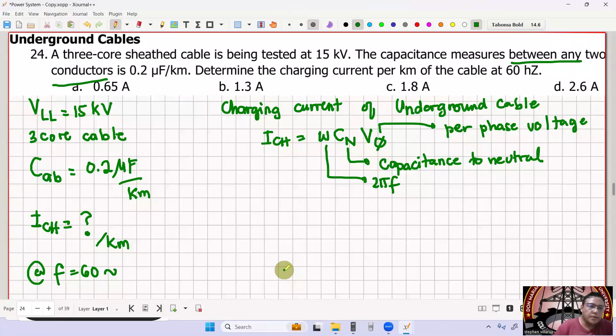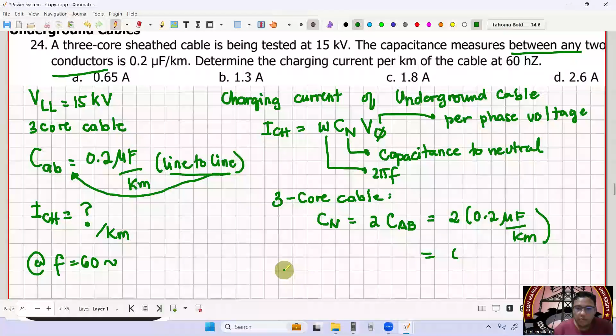Hindi siya line-to-neutral or capacitance to neutral, so paano natin yan kukunin? Take note po, for a 3-core cable, yung capacitance to neutral is equal to twice ng capacitance of the line to line. So this is now equal to twice 0.2 microfarad per kilometer, therefore this is now 0.4 microfarad per kilometer.